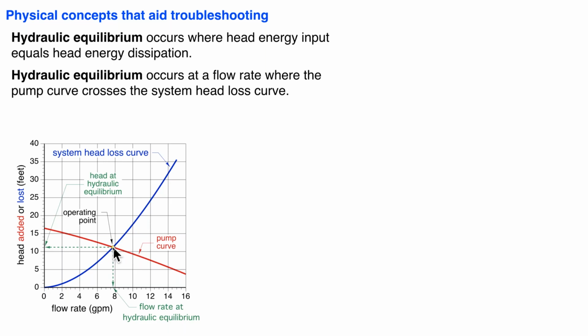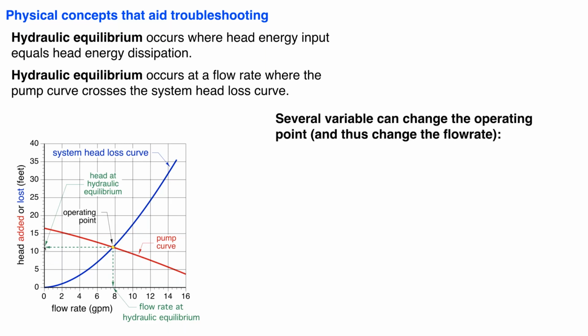It's very useful because if we just drop a line down here, we can read what the flow rate in the system should be. And likewise, we could go over here and get head, and we could convert head to delta P. And actually, if you had differential pressure gauges, you could measure that. So again, if you're not getting the flow rate that you expect to have, think about how that circulator curve and that system head loss curve interact. And there are several things here that can change that operating point in a system.